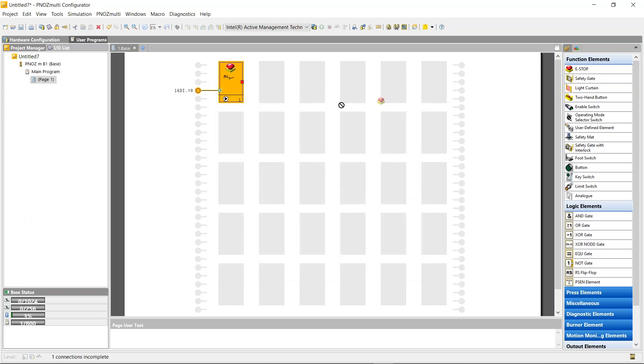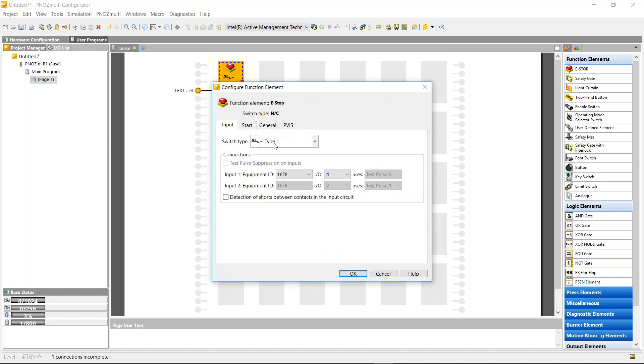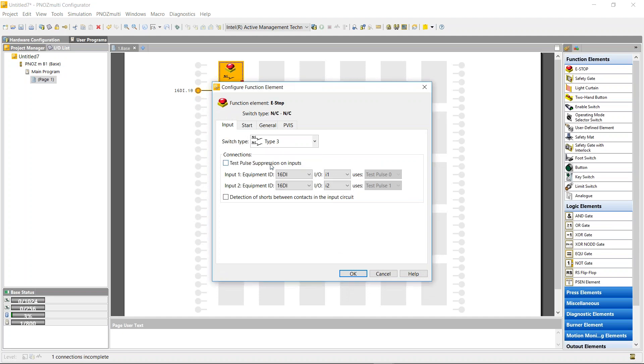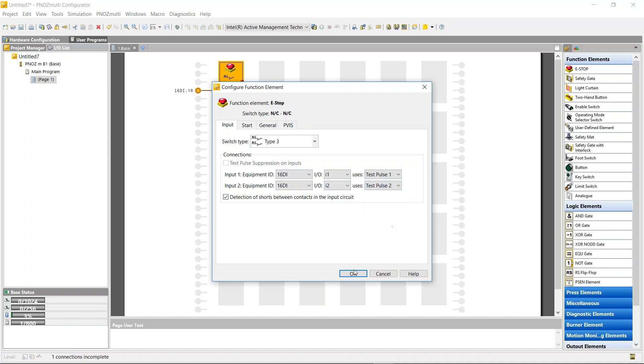The next e-stop I'm going to use is type 3, two normally closed. Same thing again, I'm going to put it into the 16 digital input module at i1 and i2. I'm going to use detection of shorts, pulse 1 and test pulse 2.